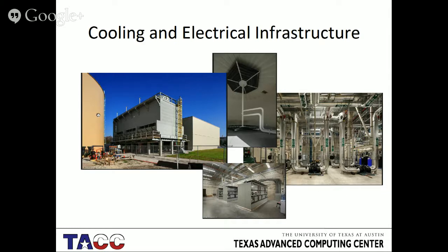So when we built this new cooling facility, to save money on power, what they did is they also built this huge insulated tank. So overnight, what happens is the chillers chill more water than is needed and pump it into the tank. During the hottest part of the day, from about noon to 4 or 5, the chillers shut off. And the chilled water we use is what comes from that tank. Because this is also the time of day when electricity is the most expensive.